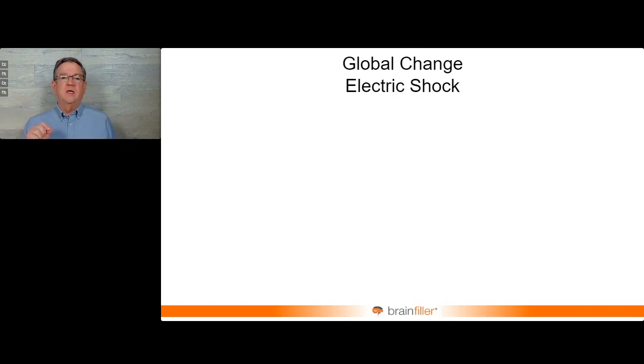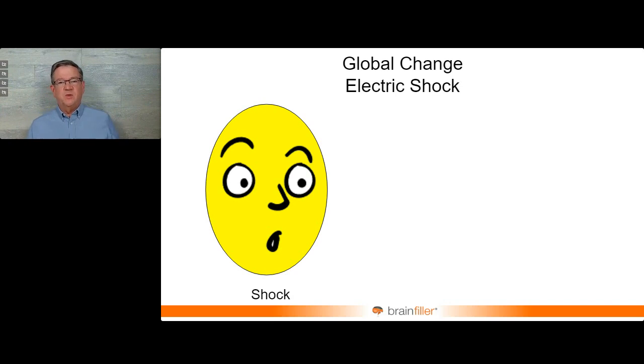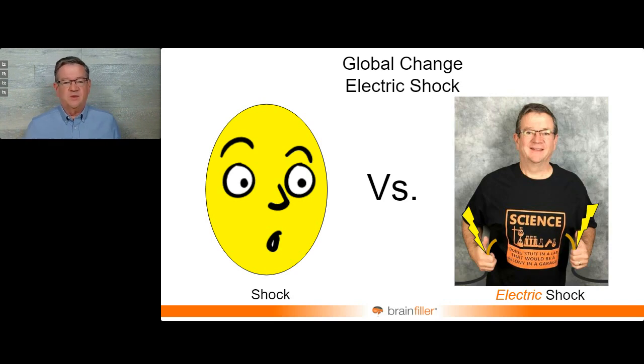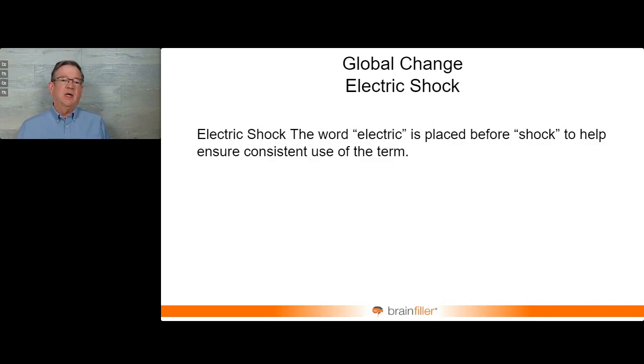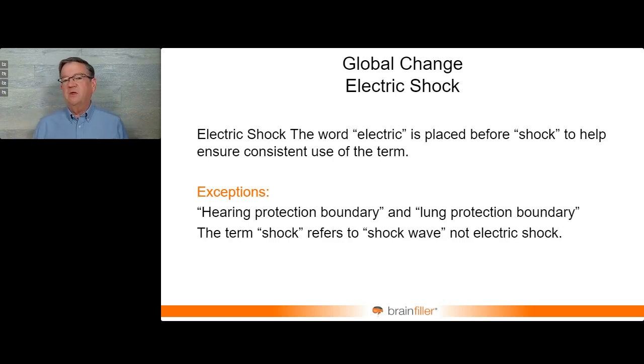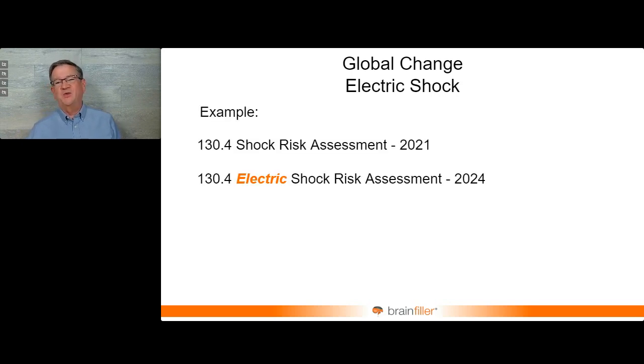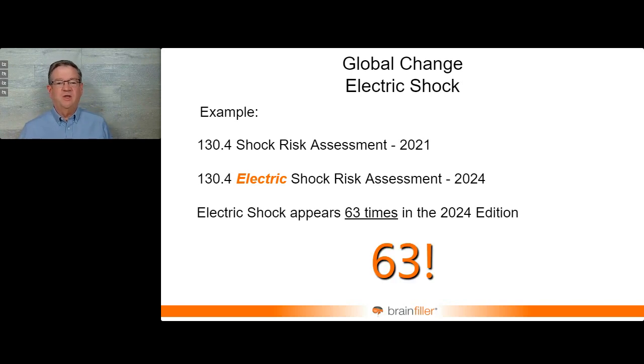And one of those changes is changing the word shock to electric shock, because historically shock is what's been used, but is it like, whoa, I'm shocked? Or is it this kind of shock? I wouldn't advise doing something like that. And so the word electric was added to shock. And the only exceptions, there are still 2 places where you'll see the word shock and electric is not in front of it. And that's when we're talking about a shock wave. So the hearing protection boundary, the lung protection boundary, both use the word shock, but they're referring to shock wave. Everywhere else, it is electric shock. And this actually occurs 63 times in the 2024 edition of NFPA 70E.